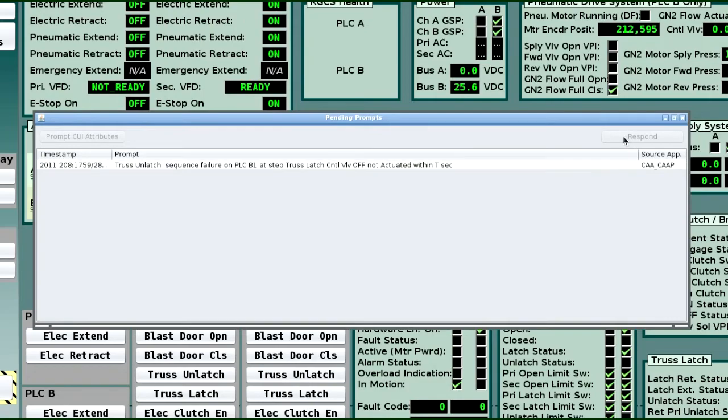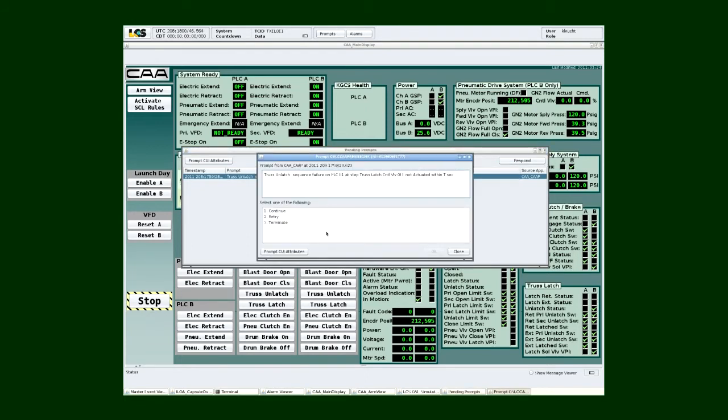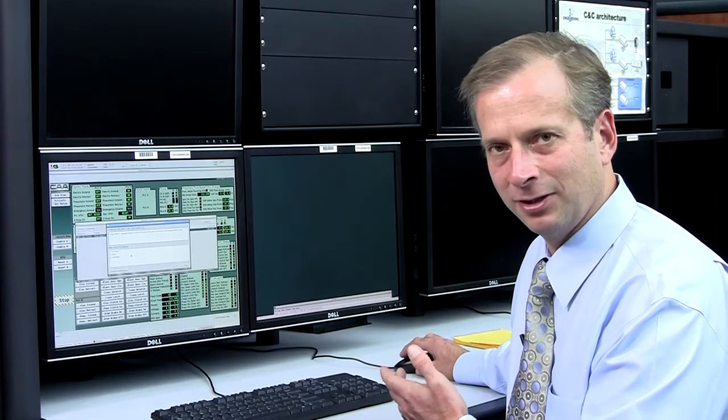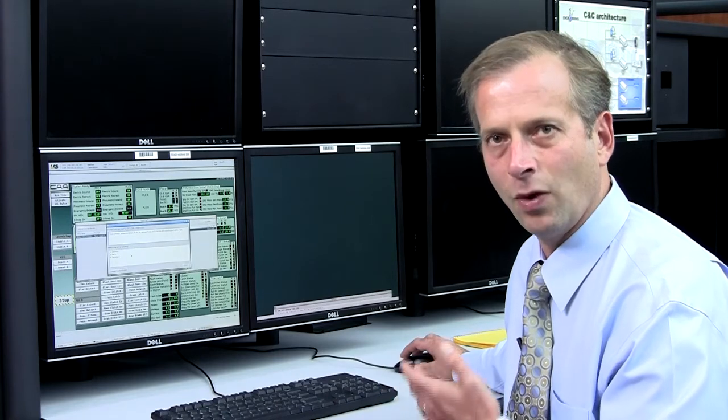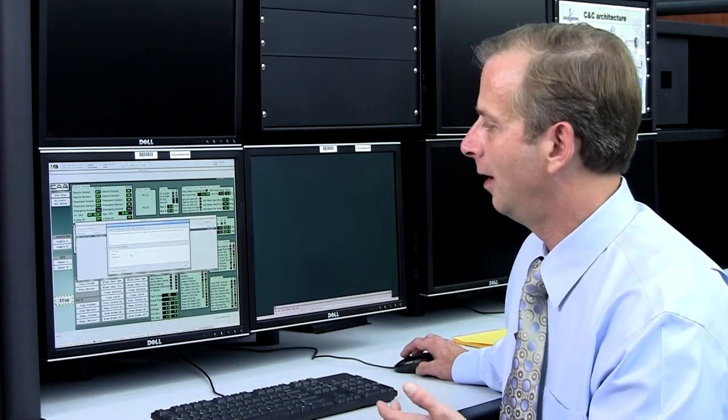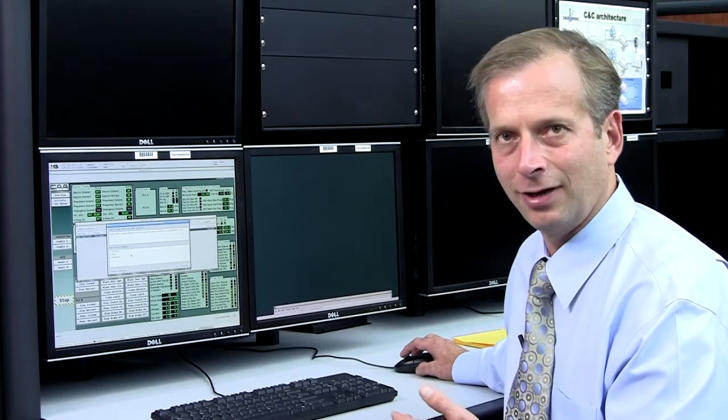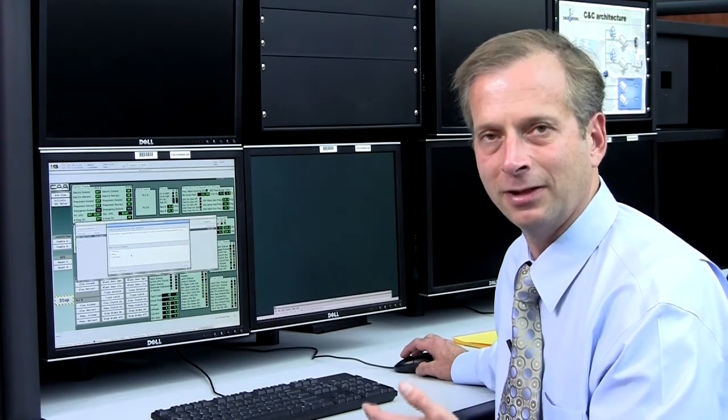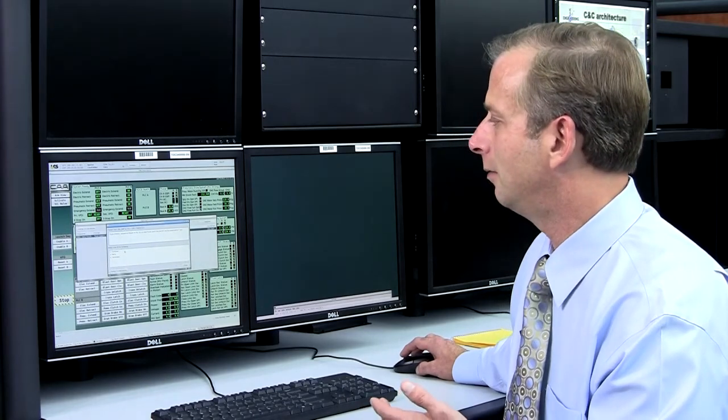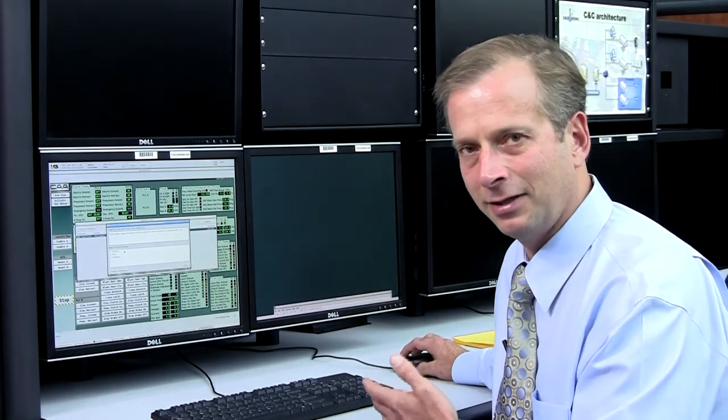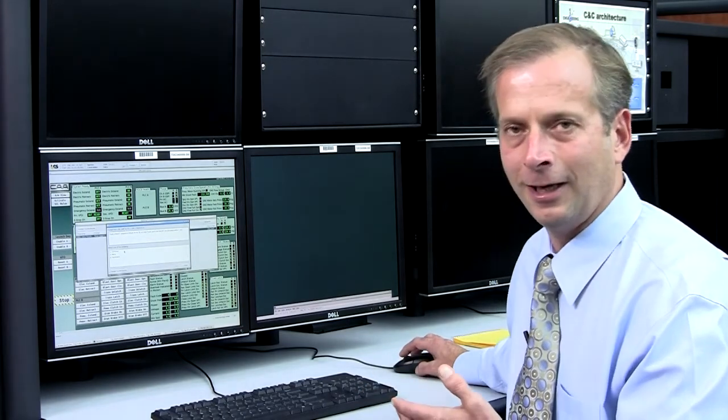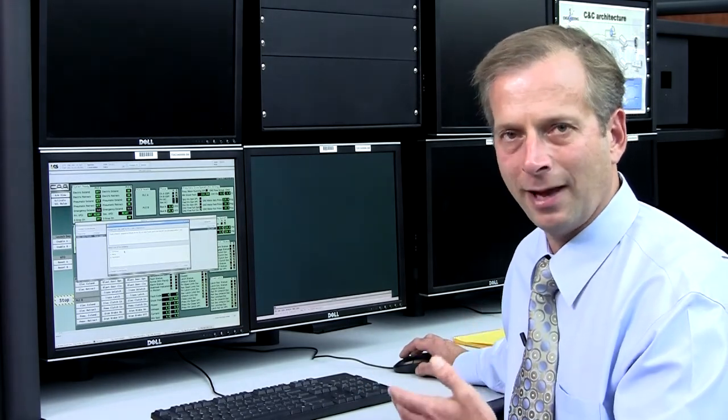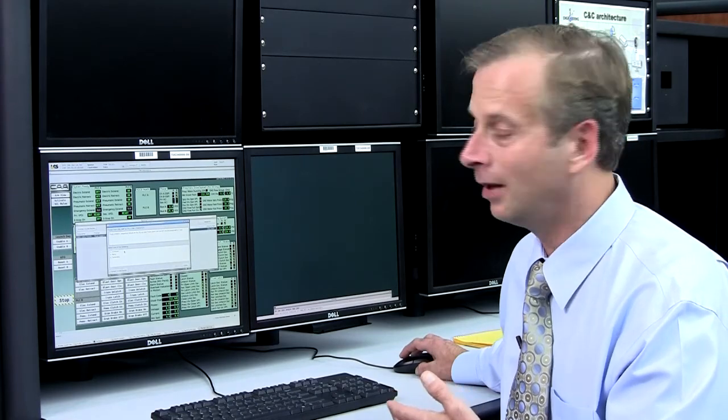I can choose to respond to this particular error. So I have to select my error and select respond. And when I select respond, it gives me currently three different options. I can select continue. I can select retry. Or I can terminate my sequence. The difference between continue and retry is if I retry, this system is going to provide a handshake to the PLC to tell it to wait for that particular limit switch to report off. So you can actually try to see if a particular piece of hardware responded, but possibly is responding too slow.